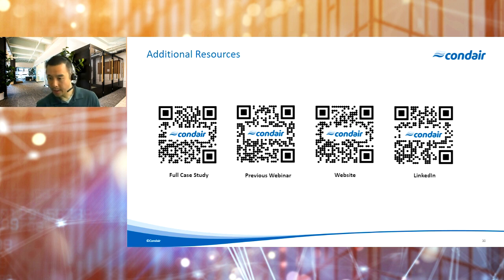Perfect. Thanks, Sean. There's a question here I can answer. Can you elaborate on ways to achieve tighter control with the evaporative media humidifiers? Can it achieve plus or minus 2% at 70 degrees Fahrenheit? So, yeah, we had talked about that just very briefly, but one way you can improve the control accuracy with an evaporative media system is by using bypass control. So either having bypass dampers above or to the side of the unit or in the middle of the unit, or even face and bypass dampers. And really what that is allowing us to do is control to a mixed air condition downstream after the humidifier.